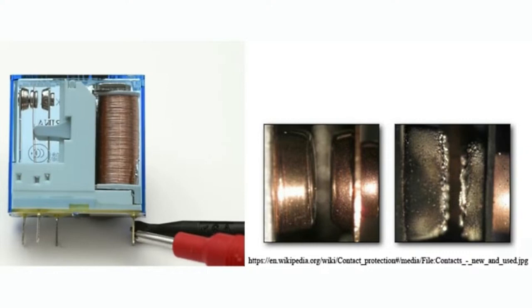On the middle left, that's what a clean contact set looks like. On the middle right, that's what corroded contacts look like. And so a lot of relays are designed to be plug-in, to unplug them and replace them when they've reached their life limit. So often, the local stoplights stopped working. It's because the relays inside broke and they just have to be replaced.